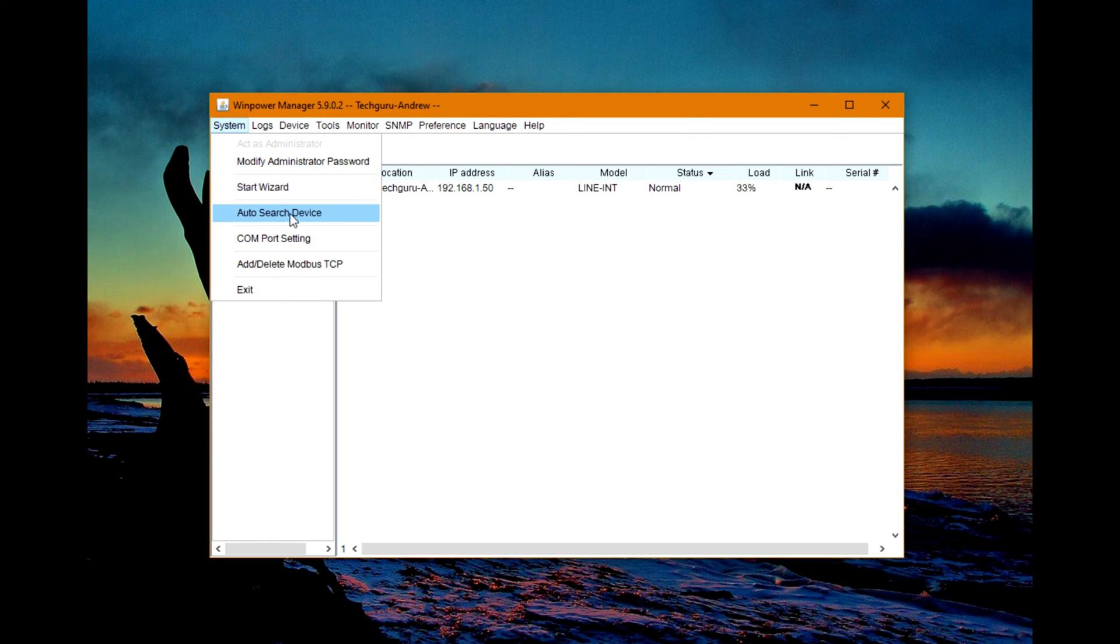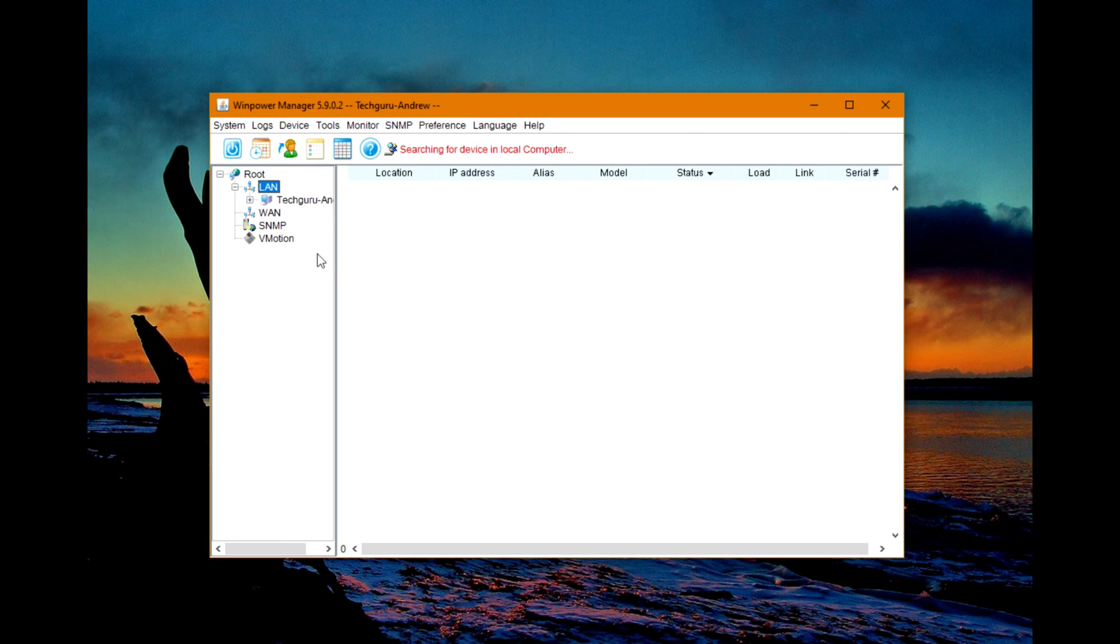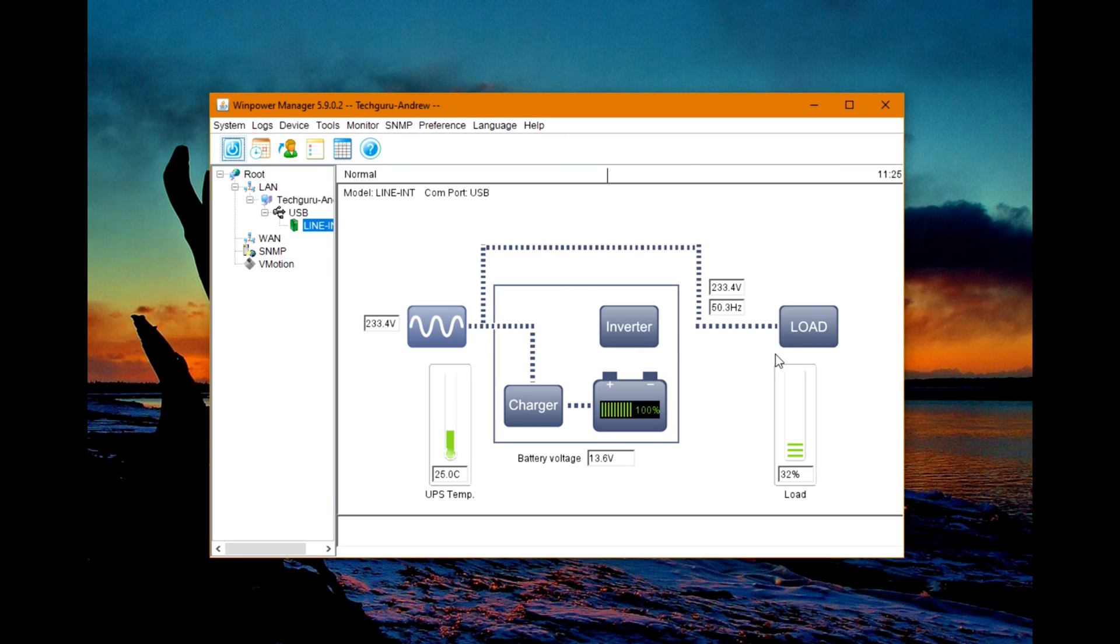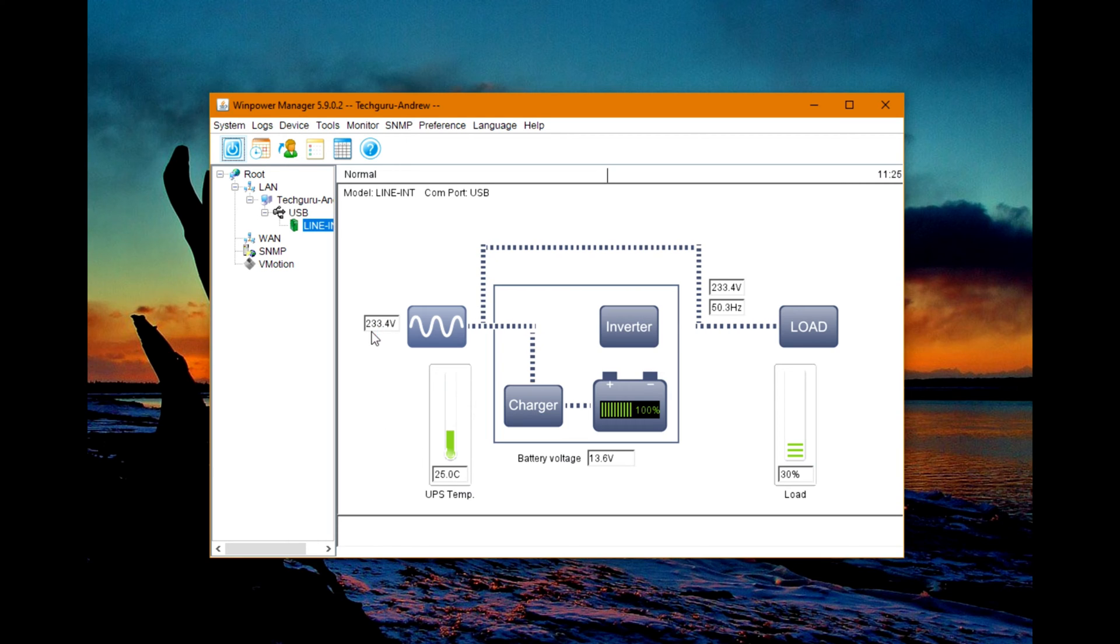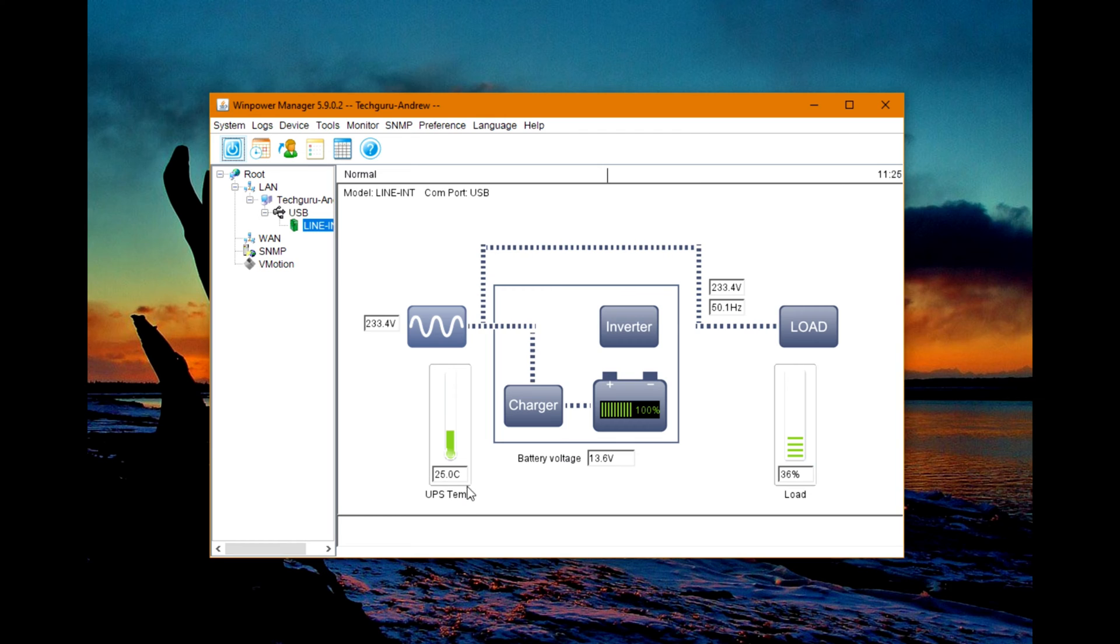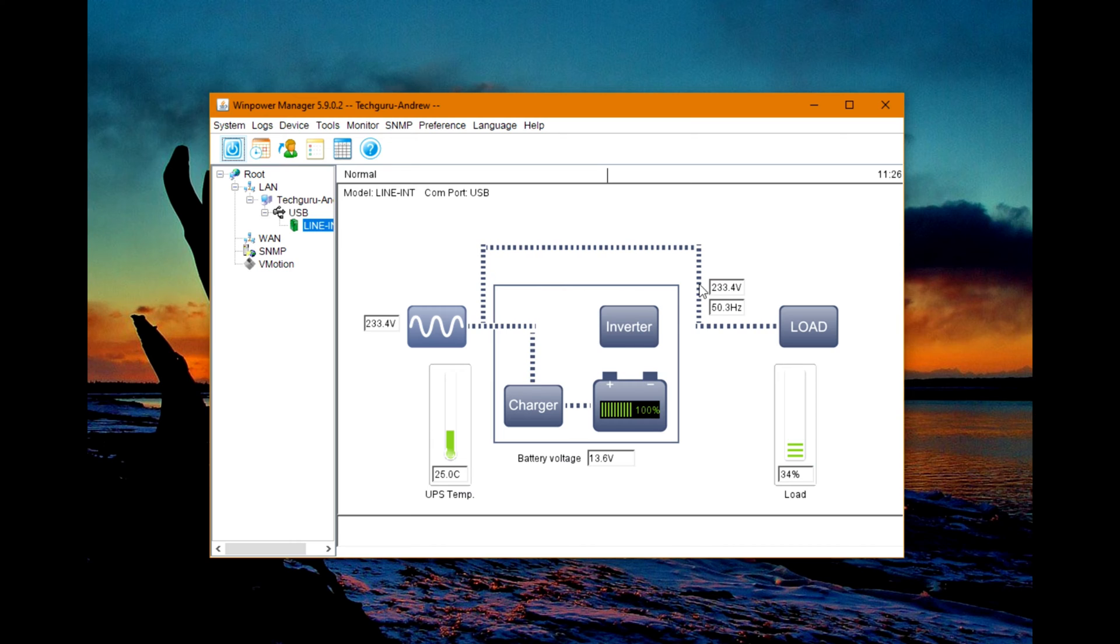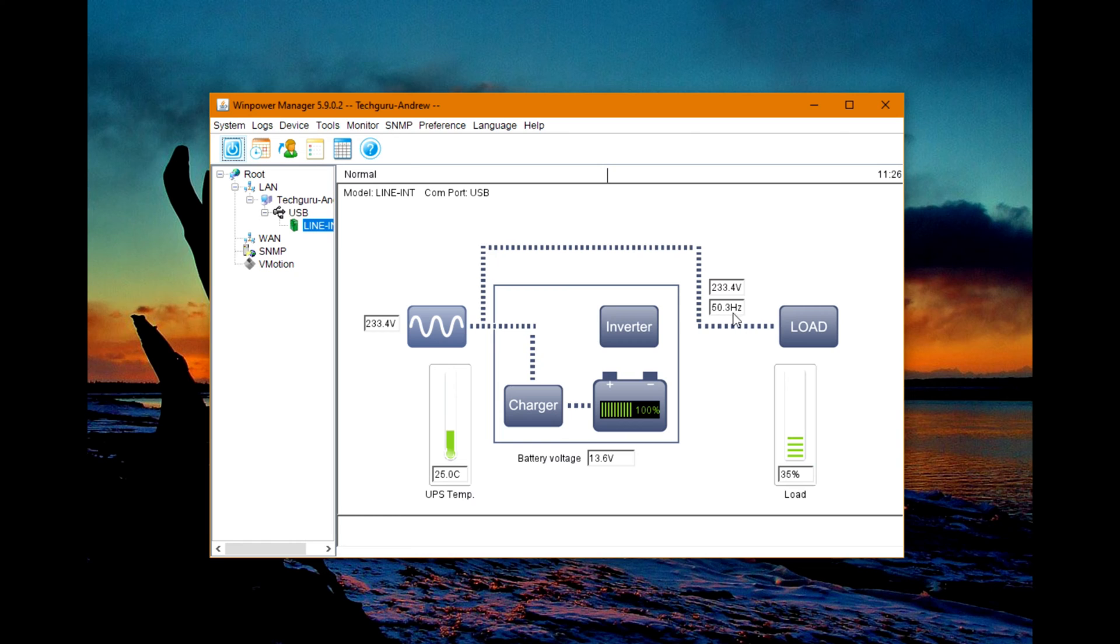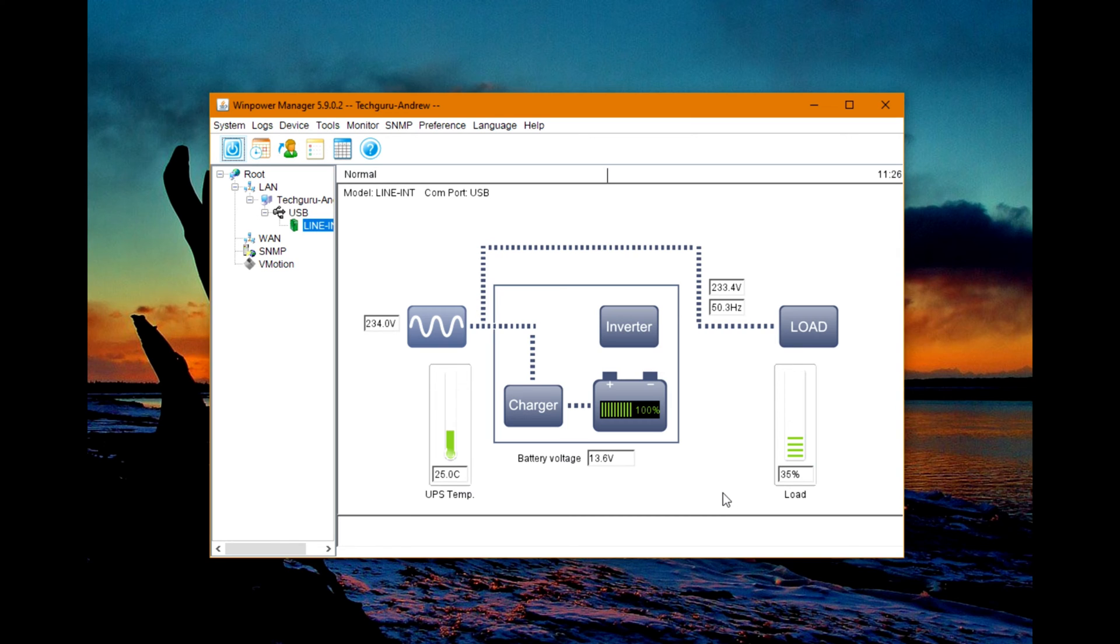Then you can go to Auto Search Device, and here you can see it's searching for devices on the local computer. Here's the UPS - just double click. On the first look, we can see the input voltage is 233.4 volts, UPS temperature 25 Celsius, battery voltage 13.6 volts at 100 percent capacity. The load voltage is 233.4 volts at 50.3 hertz, and the load is 35 percent. It goes up and down depending on what you're doing on your desktop.